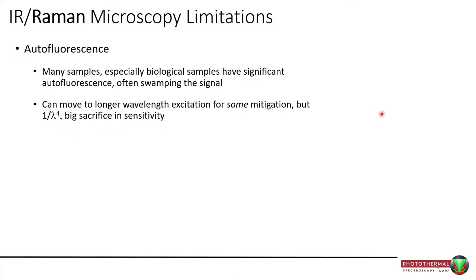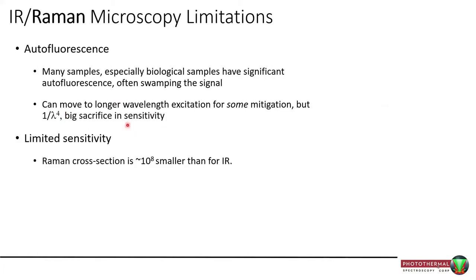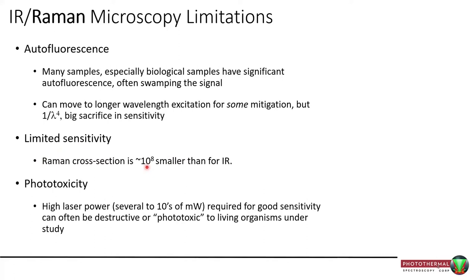On the Raman side, there are also technical limitations from maturity. Autofluorescence can swamp the signal — any Raman practitioner knows this well. You can mitigate some of that by going to longer wavelengths, but you lose a large amount in sensitivity. Limited sensitivity is a fundamental issue; the cross-section is 10 to the 8th smaller than for IR. And if you're doing live cell work, phototoxicity can be an issue, especially pumping in tens of milliwatts.